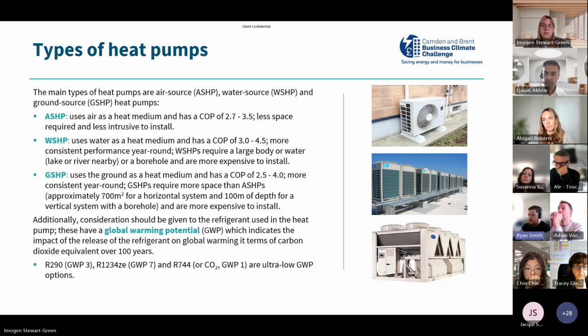It's just the medium of which that might vary. So there's a term called coefficient of performance with heat pumps as well, so COP. That's essentially the efficiency. So if you consider a conventional gas boiler, that might be in the region of 80 to 95% efficient. With a heat pump, you're getting between 270 and 350% efficient. So you're getting quite a lot of heat for the electricity you're putting in. So that's where you see the COP of 2.7 to 3.5. That's essentially what that means.